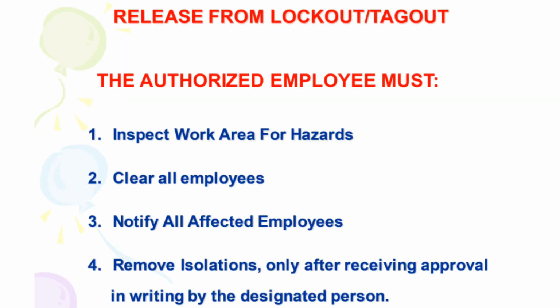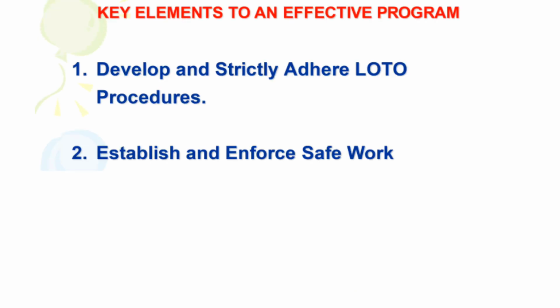Release from lockout-tagout: the authorized employee must 1. Inspect work area for hazards. 2. Clear all employees. 3. Notify all affected employees. 4. Remove isolations, only after receiving approval in writing by the designated person.